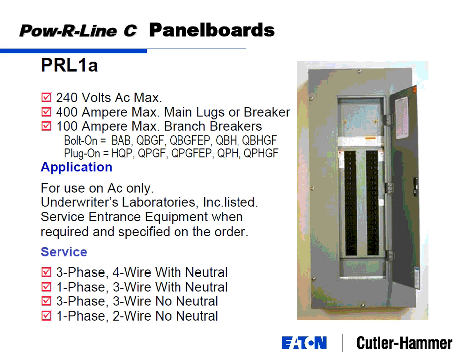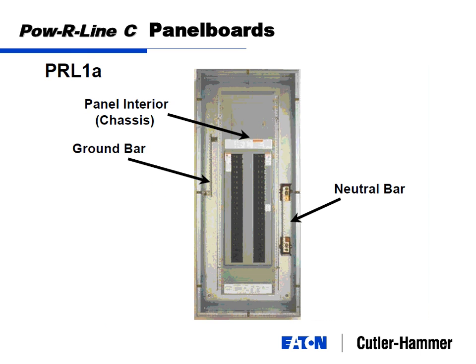So your 1A, Pow-R-Line 1A panels, again, these are 240 volt panels, 400 amp maximum. They look pretty much just like this. Your bolt-on breakers are your BAB, which is just like these. And you can stack them up one on top of the other. What it looks like installed is your chassis here inside your box, and then you will install a ground bar in one gutter and a neutral bar in the other gutter.